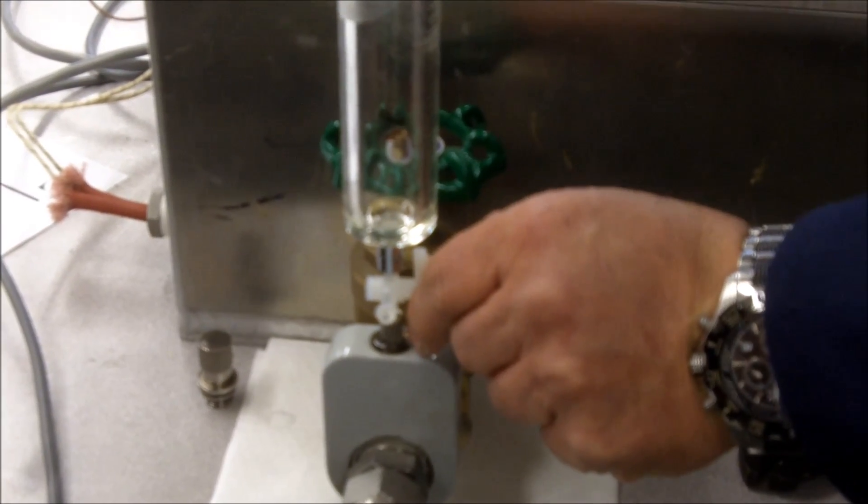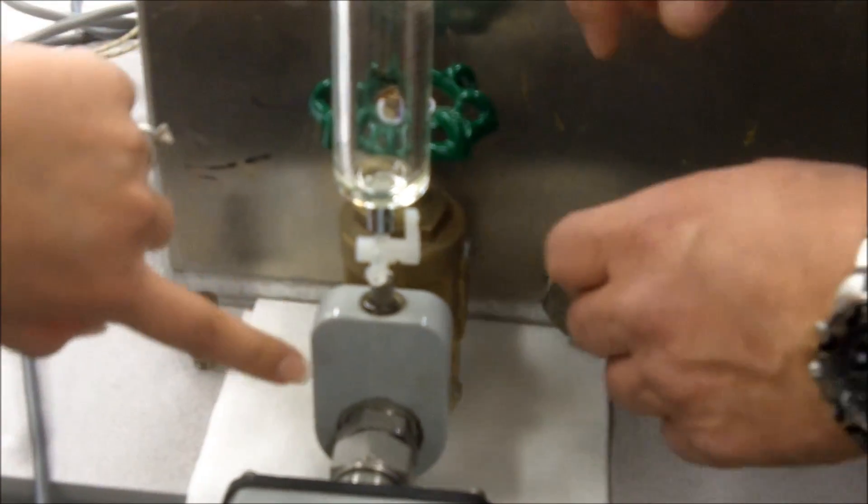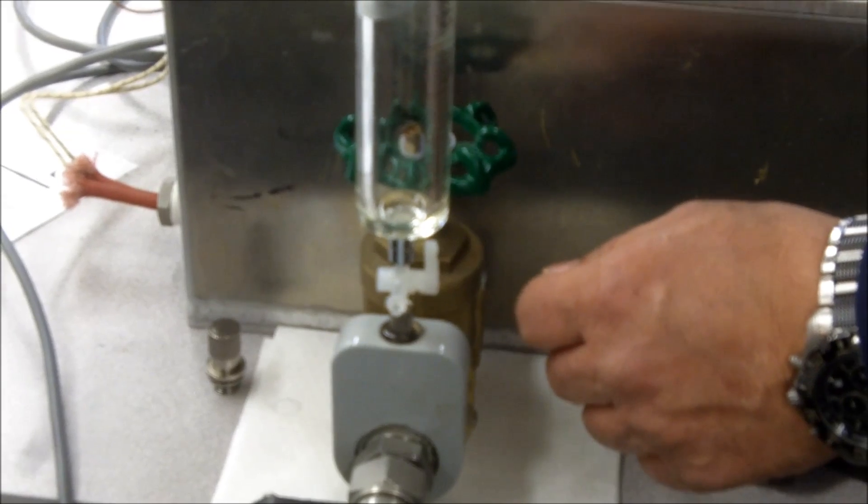Once you feel you have purged the air, do not push the air back in. You always want to make sure you have positive pressure on your transformer before you take an oil sample.